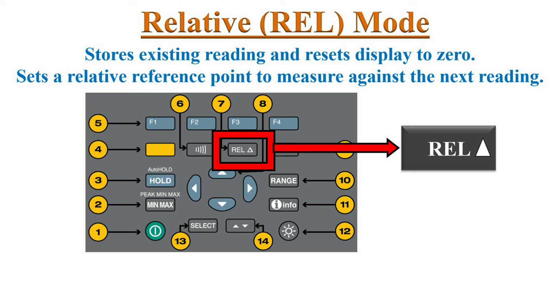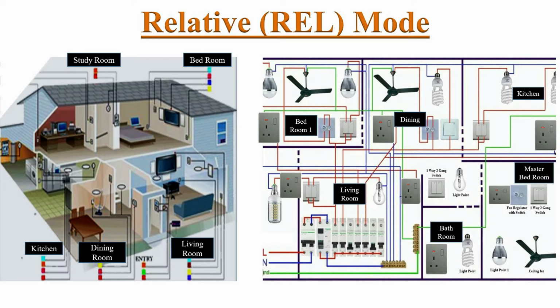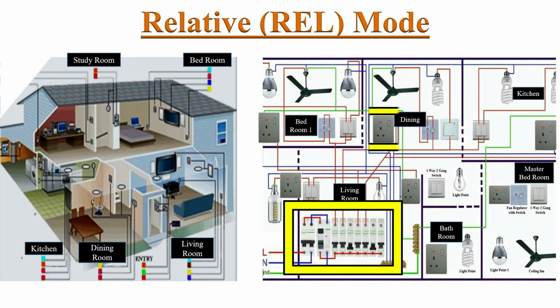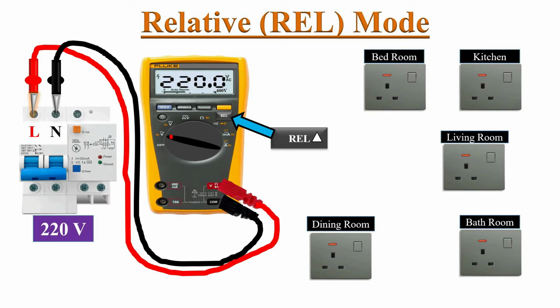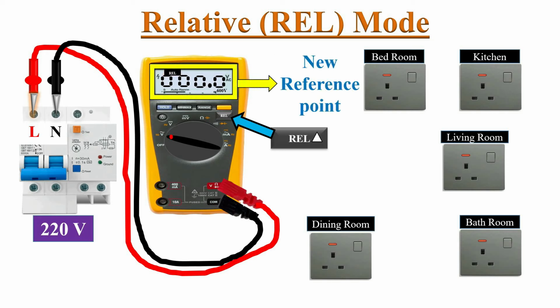Let's discuss this relative function with one good example. Just imagine power distribution in your home, from the main supply board to various wall sockets throughout your home. First, measure voltage at the main circuit breaker. Suppose it shows 220 volts. With the meter still connected to the mains, press this relative button. The relative symbol appears on the screen and immediately the reading becomes 0. What happened here is this 220 volts reading becomes the new relative measurement point for the next readings.